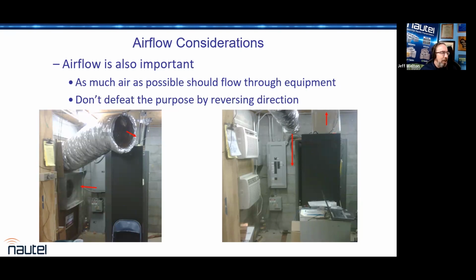The other thing I talk about a lot is airflow. This is that guy in Arkansas we saw brazing the ground system. This was the original install. They had the cold air blowing out at ceiling height and the cooler air coming back in the lower vent, and the reasoning was, well, that's how Bard does it. If you put a Bard air conditioner in a transmitter site, just know right off the bat that your air handling is upside down, because just about every broadcast transmitter on the planet exhausts hot air out the roof. I don't know about all of them, the lower power ones not so much, but the big boxes absolutely, and they'll bring cooler air in down below, whether front, back, or a combination. So that's what he had.